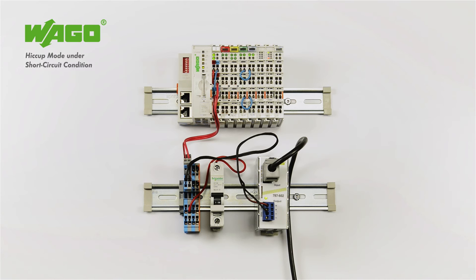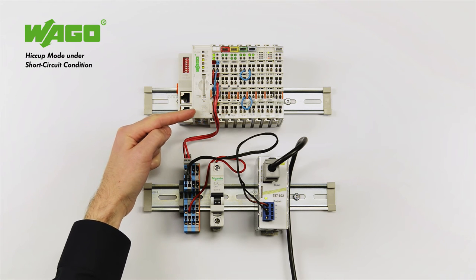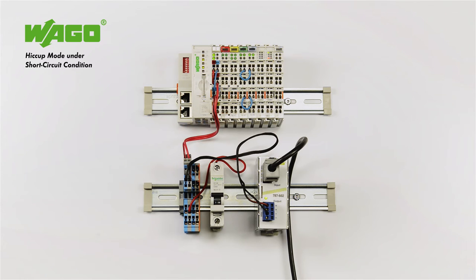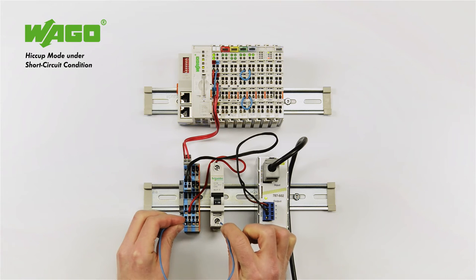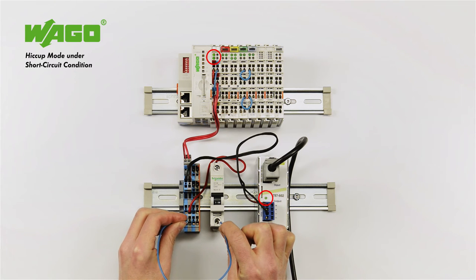In this example, we are using a power supply unit with a hiccup mode and a nominal current of 1.3 ampere, which supplies two output circuits. The WAGO I/O system is running in the first circuit, while in the second circuit we generate a short circuit directly at a C1 miniature circuit breaker. The hiccup mode is easily recognizable by the flashing LEDs.